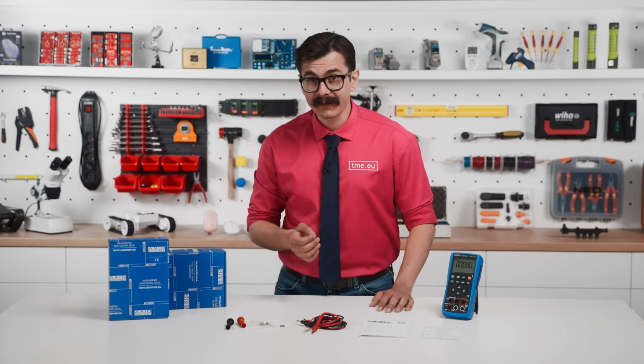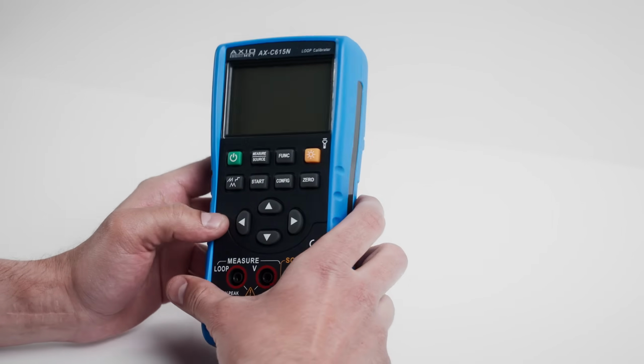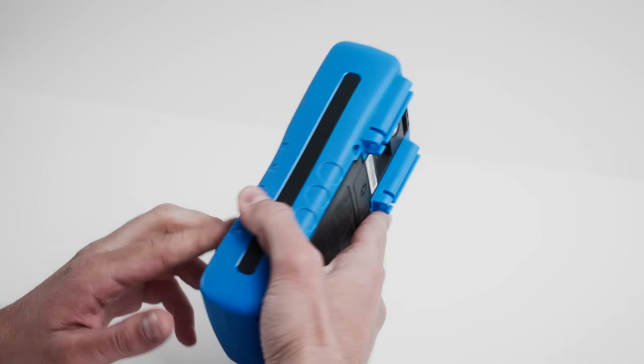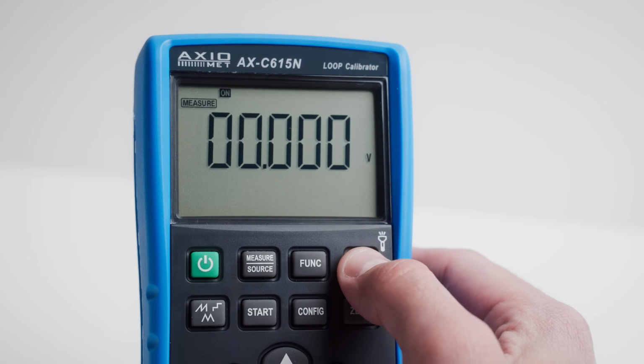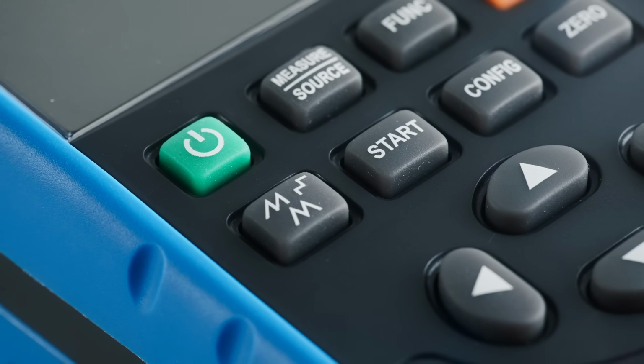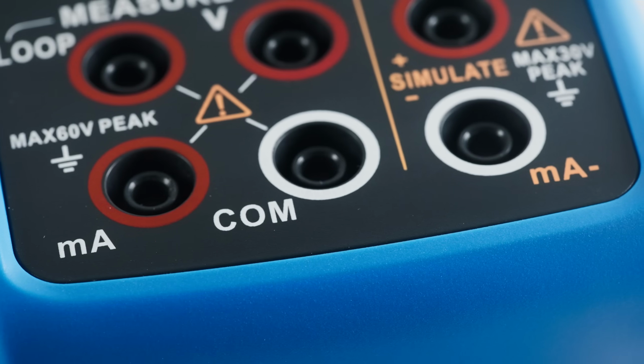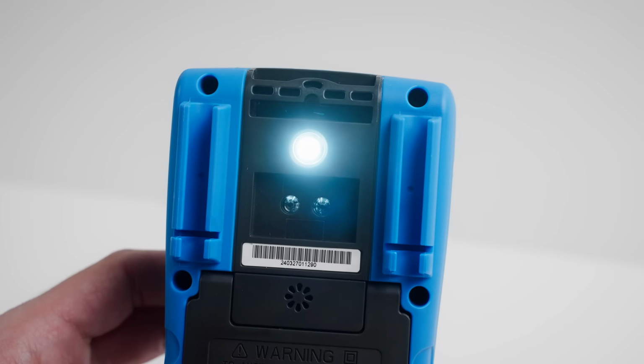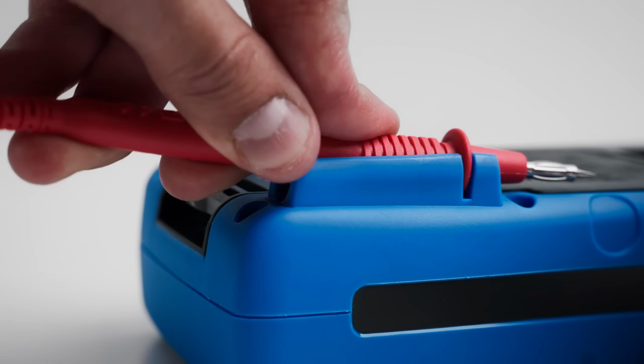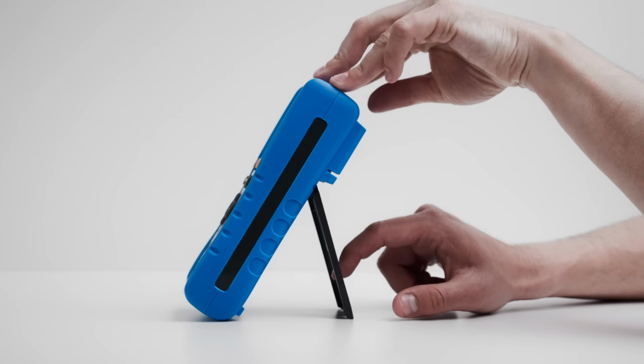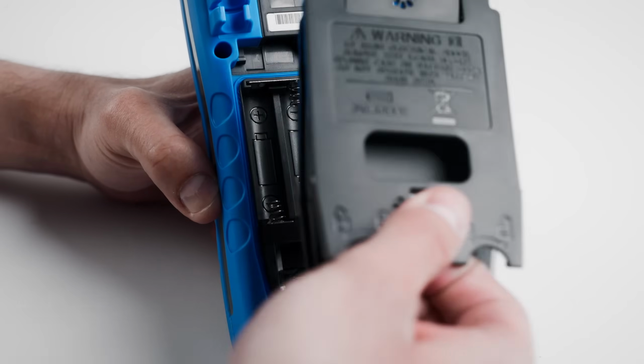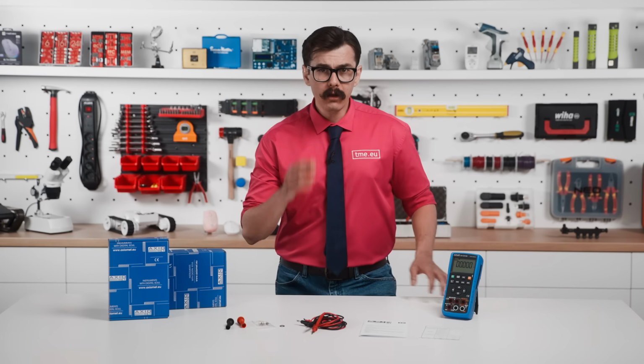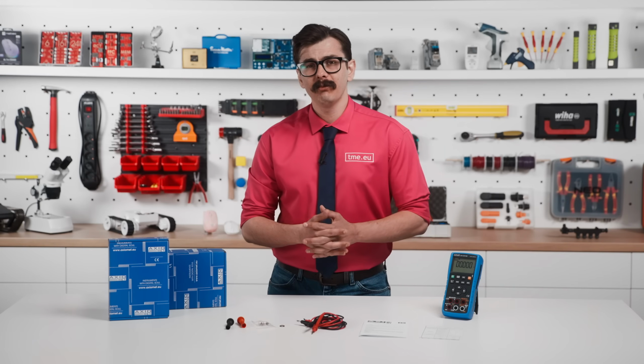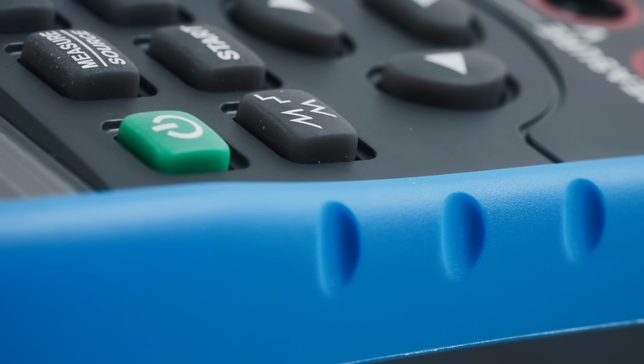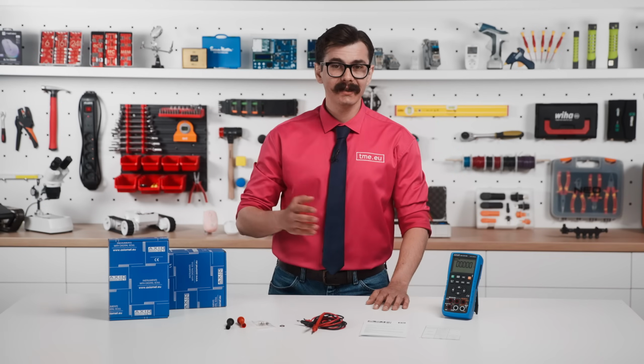From a size perspective, it is not the smallest calibrator, but because of that, it's actually quite comfortable to use. You get a large backlit LCD, big function buttons and clear terminal markings. On the back we have a hanger, an LED torch, test lead holders, a fold-out stand and 2 locks for accessing the batteries and fuse compartment. All of this is protected by an injection molding housing with a rubber coating for an extra grip. But how does it actually work?